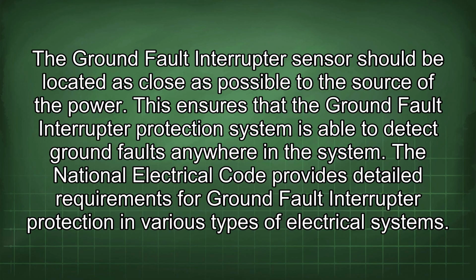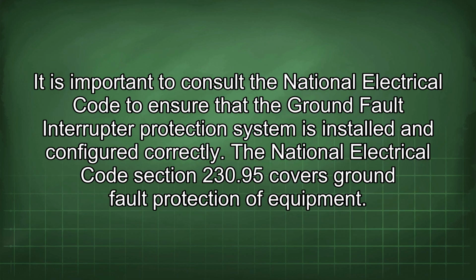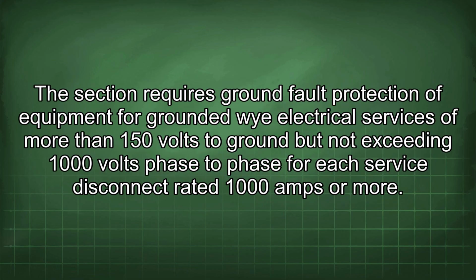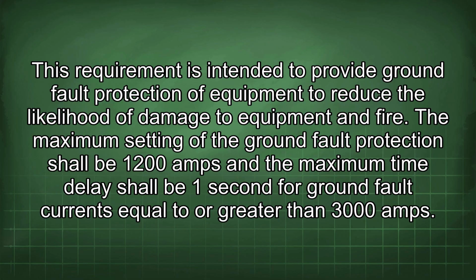The National Electrical Code provides detailed requirements for ground fault interrupter protection in various types of electrical systems. It is important to consult the National Electrical Code to ensure that the ground fault interrupter protection system is installed and configured correctly. The National Electrical Code Section 230.95 covers ground fault protection of equipment. This section requires ground fault protection of equipment for grounded Y electrical services of more than 150 volts to ground, but not exceeding 1000 volts phase-to-phase, for each service disconnect rated 1000 amps or more.